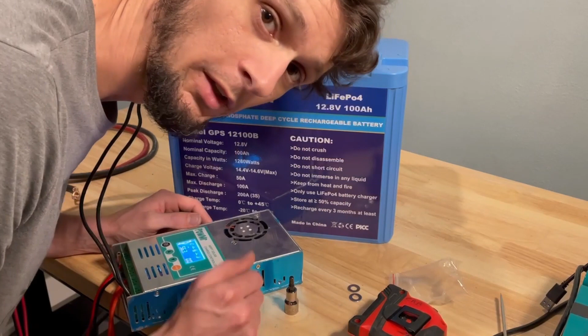All right, so we've got it plugged in here, charging. It's just about full, but what we're seeing is that we're hitting high voltage cutoff is what it looks like. So we hit 14.5 volts, and you'll see here it'll spike up to 16, 17 volts and then come right back down again. There it goes, 17 volts, back down again, 14.5. So I've currently got this set to, say here, 14.6 volts. So we're gonna set this down to 14.4, which would be the lower side of what they're saying is max.